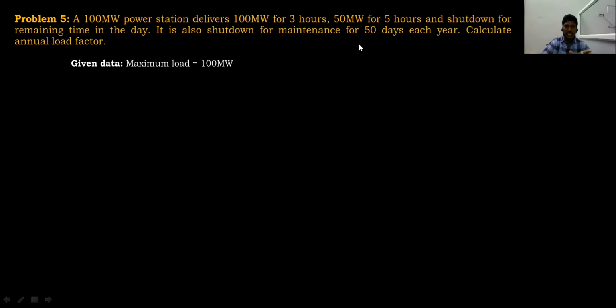Previously, we substituted 365 into 24 hours, 8760 hours, for time. But in this case, for 50 days the plant is completely shut down. So we have to substitute 315 into 24 hours in place of time. That is the difference here. The power station delivers, as per the given data, a maximum load of 100 megawatts. A 100 megawatt plant means its maximum capacity is 100 megawatts. It is loaded for 100 megawatts as well as 50 megawatts. Among those two, what is the maximum load? It is 100 megawatts, and it operates for 3 hours.